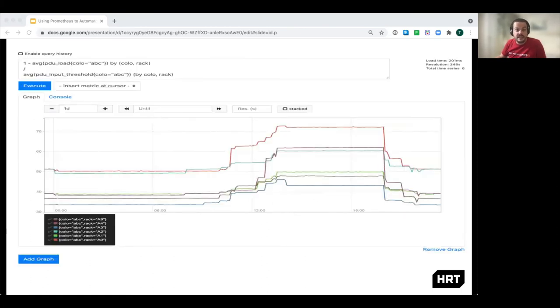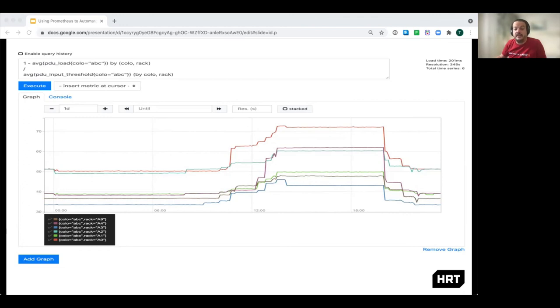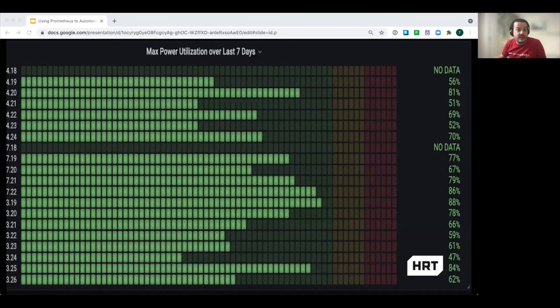Now with the consistent metric name of the load over the PDU and the per-PDU thresholds, calculating the power free in each rack is easy. From here, it's simple to even write a tool to query Prometheus to report where new servers should be racked. Even if the power load is highly variable like it is here, we can leverage Prometheus to make better capacity planning decisions. We can even use it to create nice dashboards.